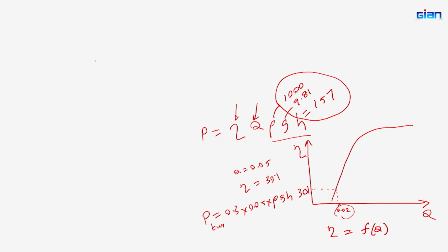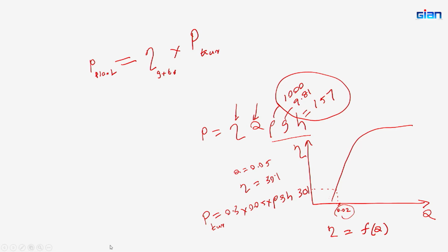So, the plant output will be efficiency of the generator plus transformer into turbine output, right, because after the turbine you have the generator and the step up transformer, for example, right. So, what is going out of the plant as the generation will be turbine output into efficiency of the generator into efficiency of the transformer, right. So, that is what we have got here.